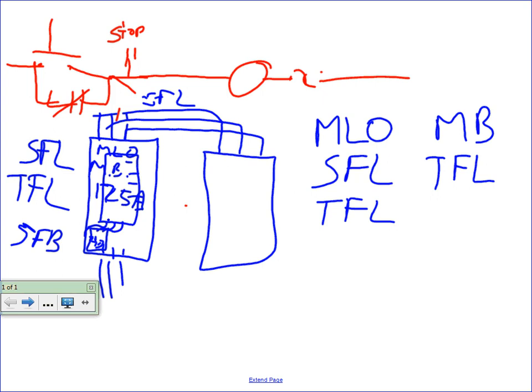So if you only have one big breaker and the rest are all small, then Q might be a better fit depending on what your fault currents are and how many big breakers. Because this would be a lot cheaper than using that I-Line distribution. And that sub-feed breaker is an overcurrent protection device. It's just a breaker with a cover, but it's mounted separately. It's not attached to the bus. It's cabled to it, but it's mounted in the panel. So there'll be a cutout in the panel where that breaker is located so you can operate the handle. But that's how we can put at least maybe one or two of those larger breakers.